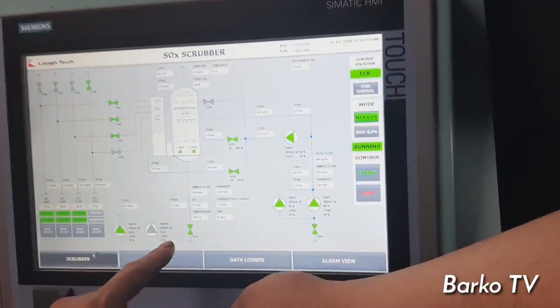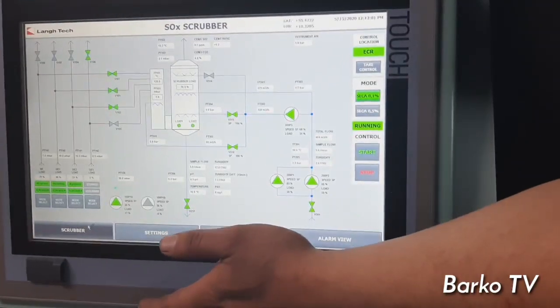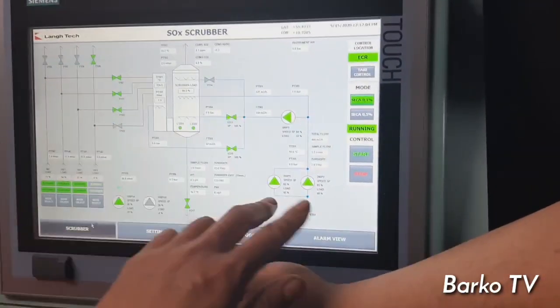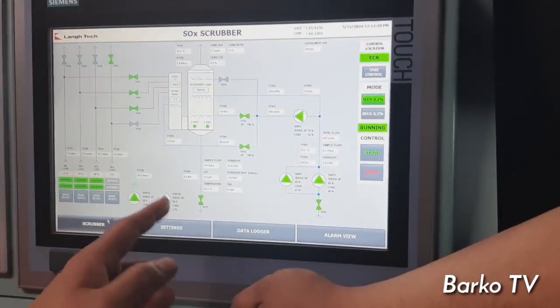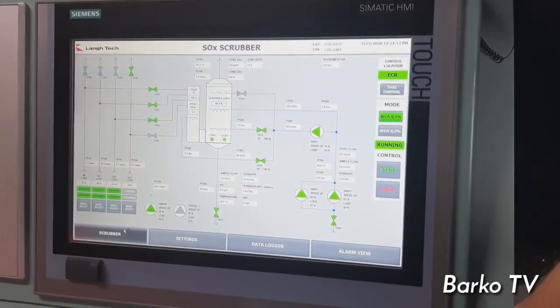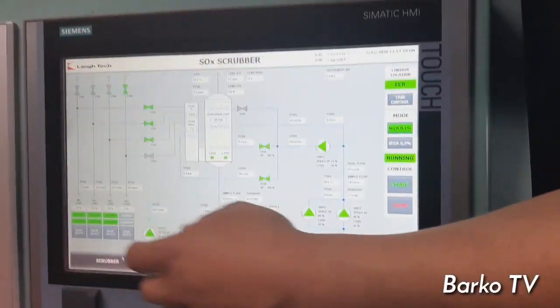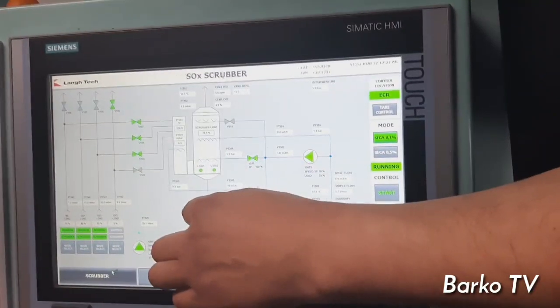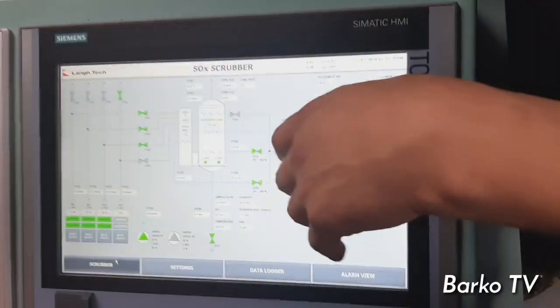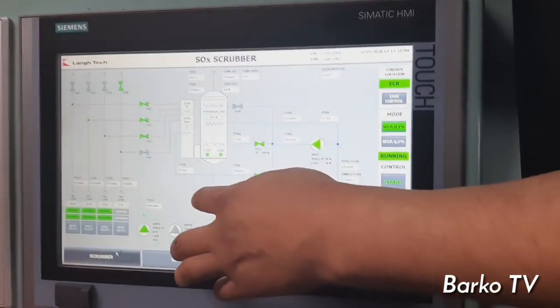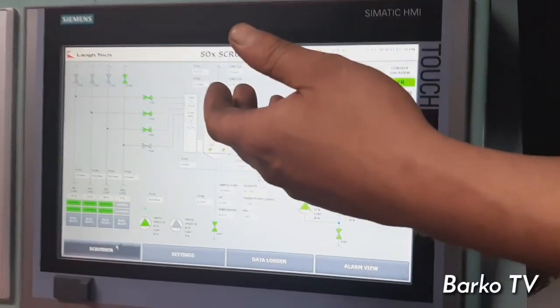This overboard valve is always full open in automatic condition. The one-bar alarm is a pre-warning that soon one of the level switches may activate and stop the pumps. If you get this alarm you have to reduce the load, and if you reduce the load the water amount also reduces. When the pumps stop, this valve will close automatically.